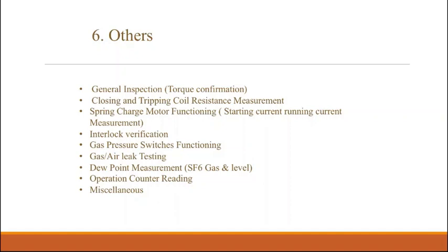And here another 3 tests I have shown: gas pressure switch functioning, gas or air leak testing, and dew point measurement. These 3 are applicable for SF6 breakers. Dew point measurement we can conduct with a particular instrument, and the leakage test we can also conduct with a leakage tester.